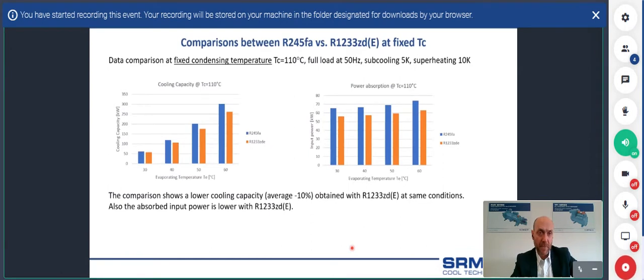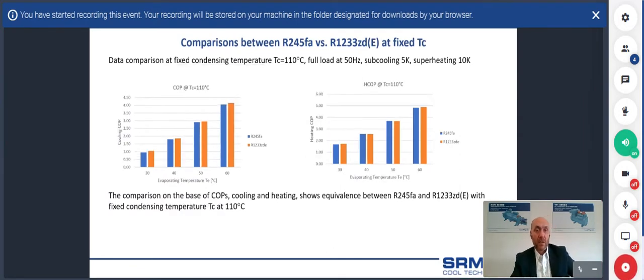The second look at the testing results is made by maintaining fixed the condensing temperature and varying the evaporating temperature. At lower evaporating temperature, the cooling capacity is practically the same, and it decreases at higher evaporating temperature. In the same way, the input power is lower for the 1233. In terms of efficiency, the two graphs are showing the heating COP and the cooling COP. These values are practically the same at a fixed condensing temperature of 110 degrees C. Another confirmation that the 1233 can be a replacement for the 245FA.